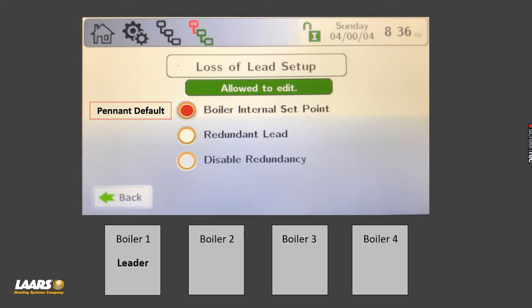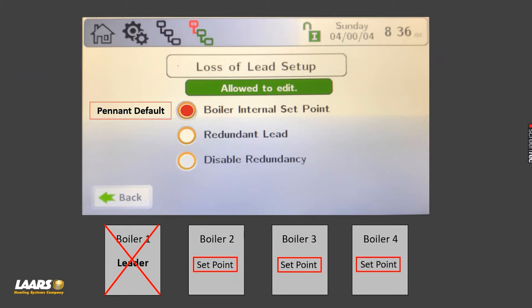Lastly is boiler internal setpoint, and that is how the Pennant is defaulted. That means if you go in and give each boiler an internal setpoint and choose boiler internal setpoint, they'll come on and operate. If somebody had to power off the leader, your member boilers or lag boilers would come on and operate on their own outlet sensor based on whatever temperature you set. The lead boiler will need to be firing and calling for the member boilers — when the lead boiler gets powered off, the member boilers will then come on and operate on their own internal setpoint.